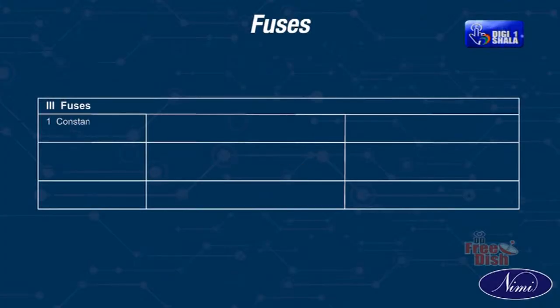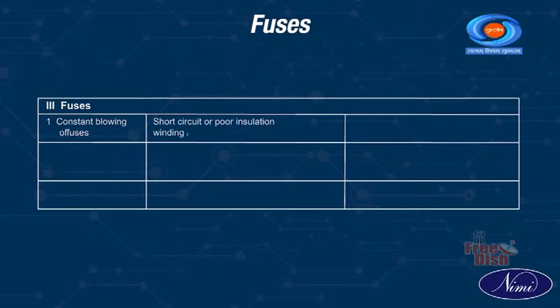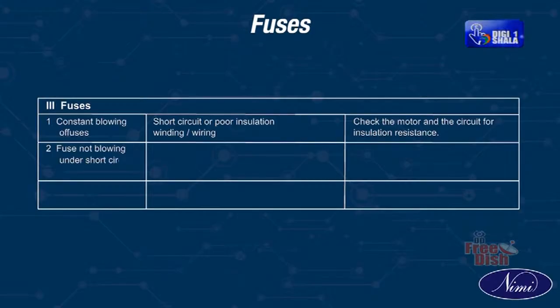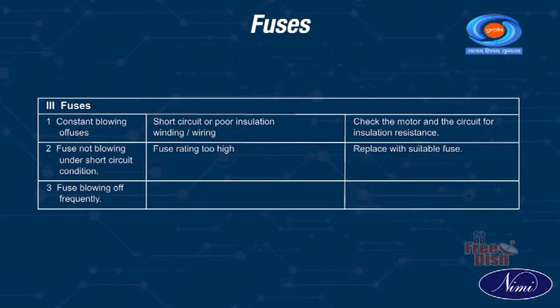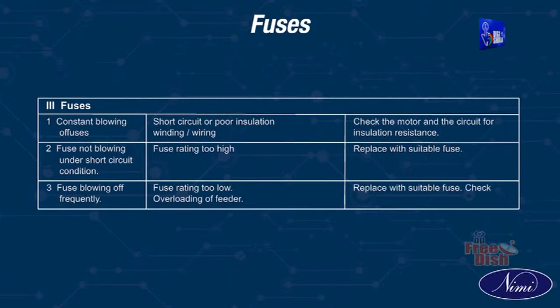Fuses. Number 1. Constant blowing of fuses. Short circuit or poor insulation in winding or wiring. Check the motor and the circuit for insulation resistance. 2. Fuse not blowing under short circuit condition. Fuse rating too high. Replace with suitable fuse. 3. Fuse blowing off frequently. Fuse rating too low. Overloading of feeder. Replace with suitable fuse.